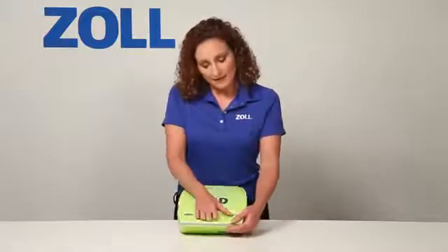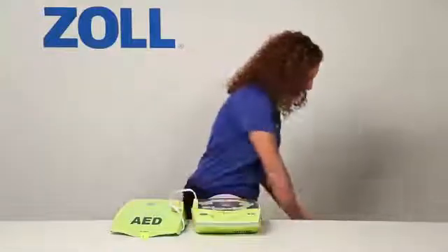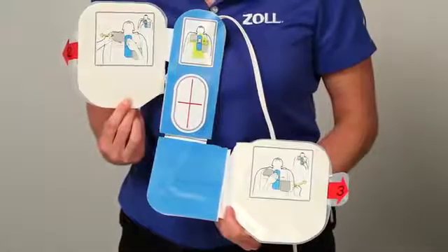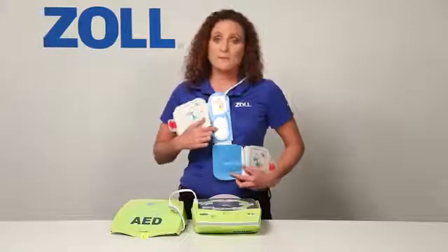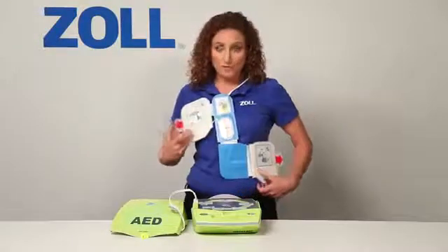It provides the best support to someone who is rescuing a victim of sudden cardiac arrest. Most of what I will demonstrate is not available in any other AEDs. Here we have several graphical icons. When I turn on the AED Plus, it will provide an audio prompt and light the icon for each rescue step. These are CPR-D pads, which are quite different from the two electrode pads found on other AEDs — they are designed for fast, accurate electrode placement. The red crosshair is a placement landmark: put it in the middle of the chest, directly between the victim's nipples, and the two electrode pads will fall into place naturally.